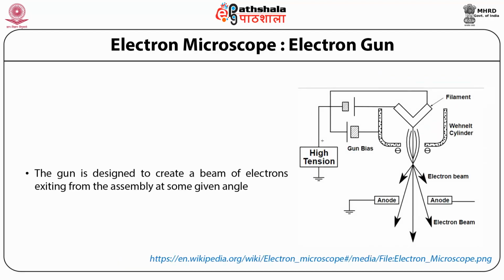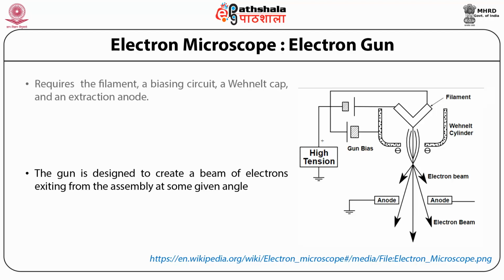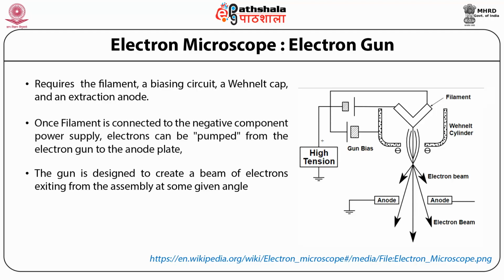Electron gun. As the source of illumination in an electron microscope is an electron beam, this electron gun is used to generate it. It requires a filament, a biasing circuit, a Wehnelt cup, and an extraction anode. As you can see in this picture, we have a filament, we have a Wehnelt cylinder which is negatively charged, and once the filament is connected to the negative power supply, electrons are pumped through the electron gun, and then there is an anode which helps to accelerate the beam as well as direct it.